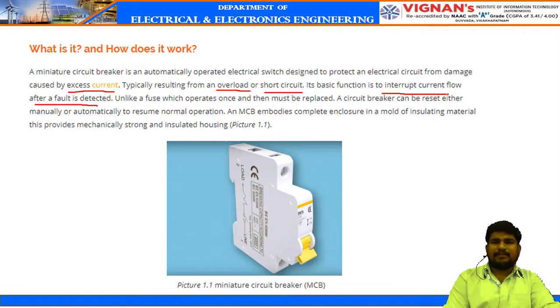For example, in the case of a fuse, we have to replace the fuse after every protecting operation. Whenever a fault or overloading occurs, the fuse will be burnt and we need to replace it. But in the case of an MCB, that is not required. Whenever there is excess current because of either overloading or short circuit, the circuit will be tripped, and a circuit breaker can be reset either manually or automatically. So this is about MCB.